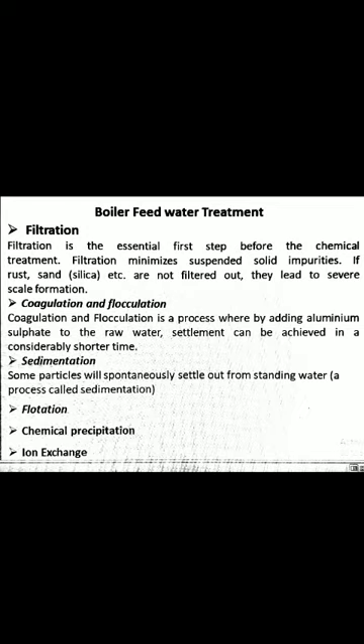The second process is coagulation and flocculation. Coagulation and flocculation is a process whereby adding aluminum sulfate to the raw water, settlement can be achieved in a considerably shorter time. Certain chemicals are added to raw water to remove impurities. While some particles will spontaneously settle out from water on standing — this is called sedimentation — others will not. To cause particles that are slow to settle to settle out more readily, a soluble chemical or mixture of chemicals is added to the water. Such a chemical is called a coagulant and the process is called coagulation.